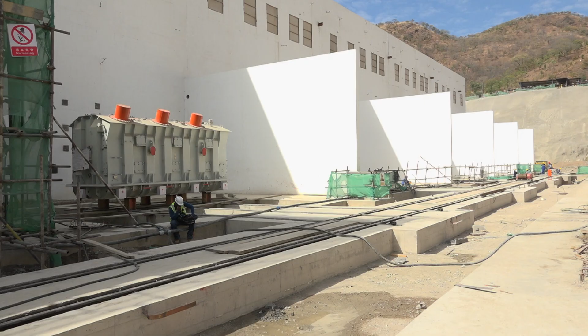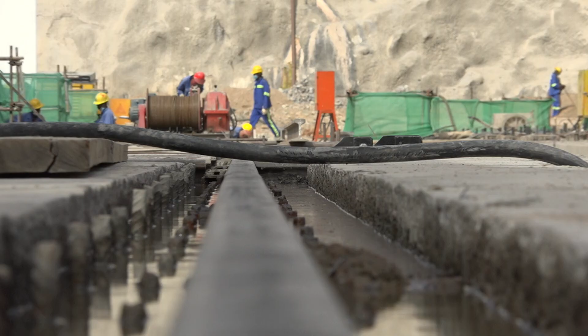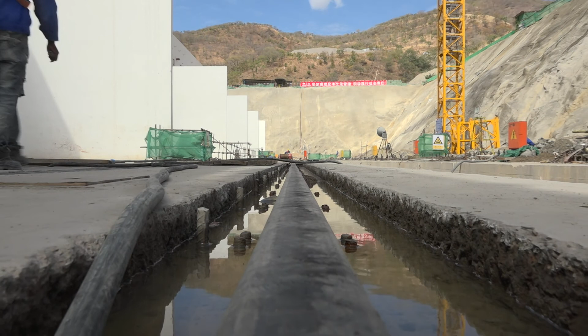The whole concept is that in case of fire, because these transformers operate at high voltage and high current and are filled with oil, a fire on any one transformer shouldn't escalate to the next. Each transformer is isolated from the one before it using fire walls. That's basically the concept behind the scope of the transformer works for this project.